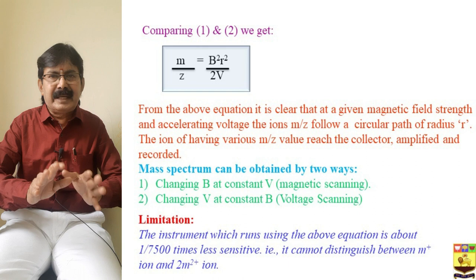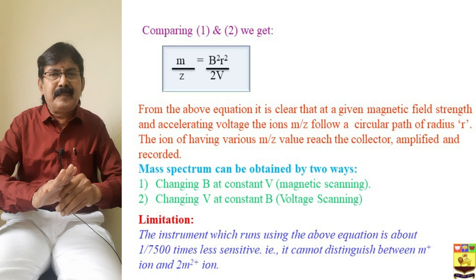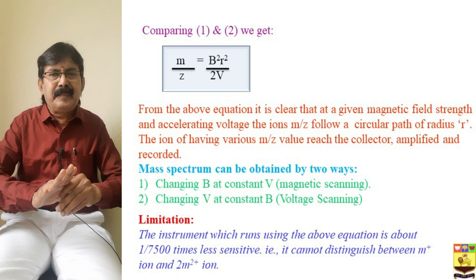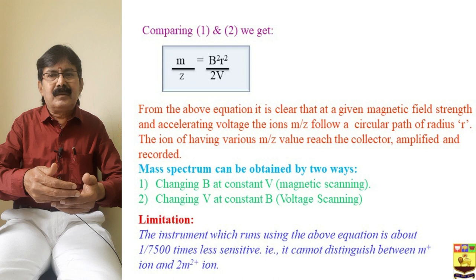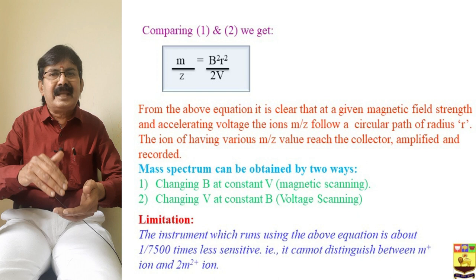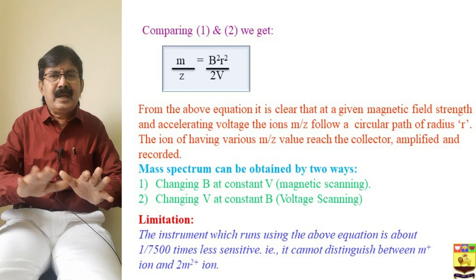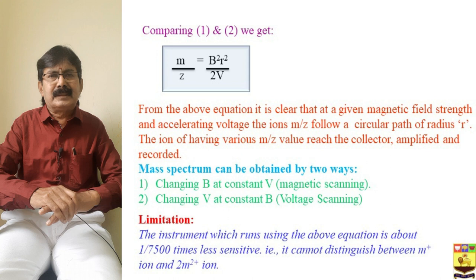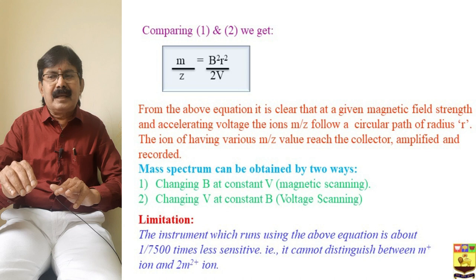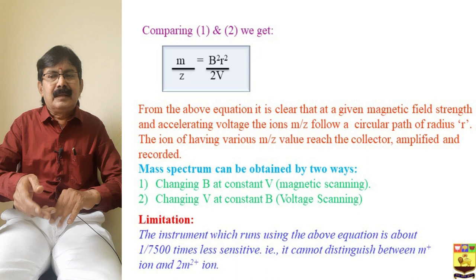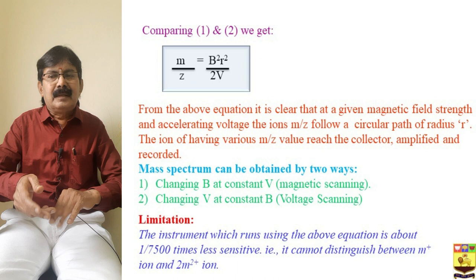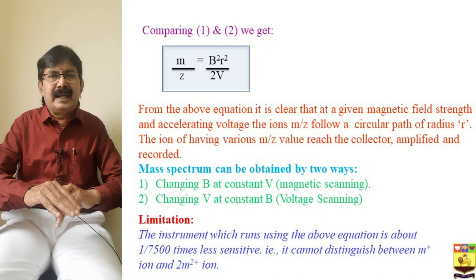From the above equation it is clear that at a given magnetic field strength and accelerating voltage, the ions of a particular m/z follow a circular path. Ions of various m/z values are separated, detected, amplified, and recorded. The mass spectrum can be obtained in two ways: first by magnetic scanning — changing the magnetic field while keeping the voltage constant — and second by voltage scanning, keeping the magnetic field constant.